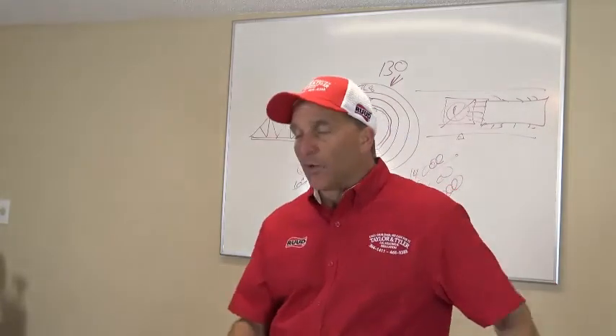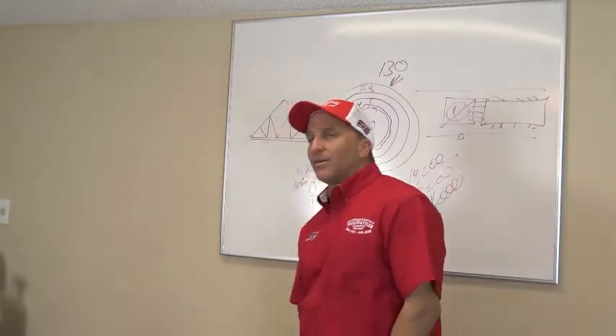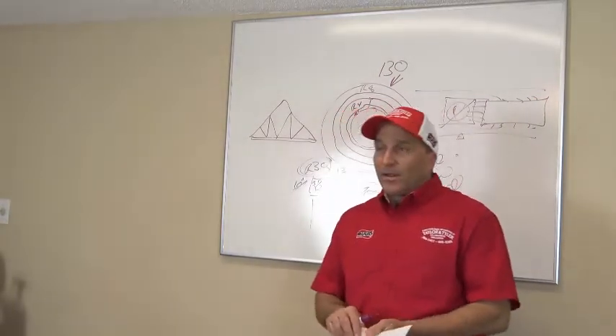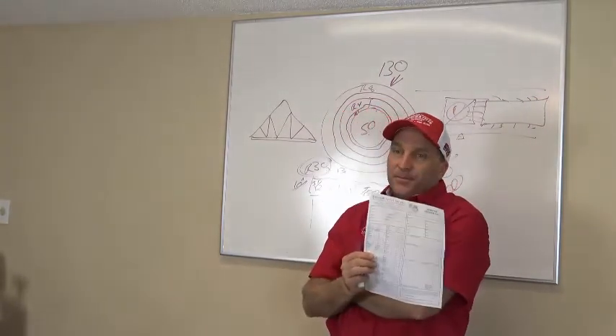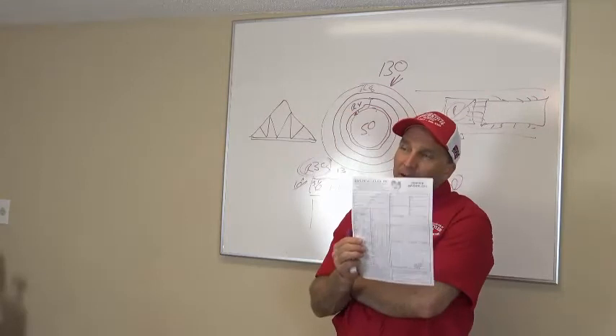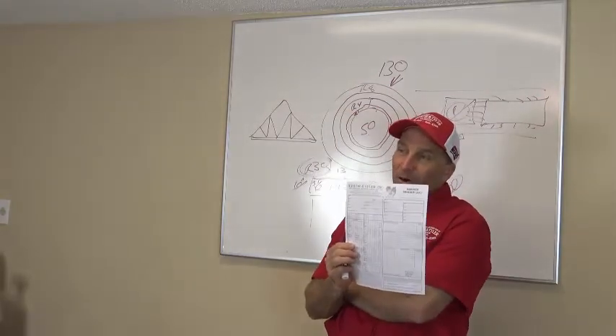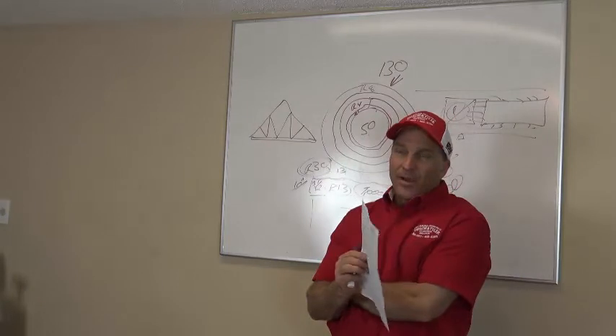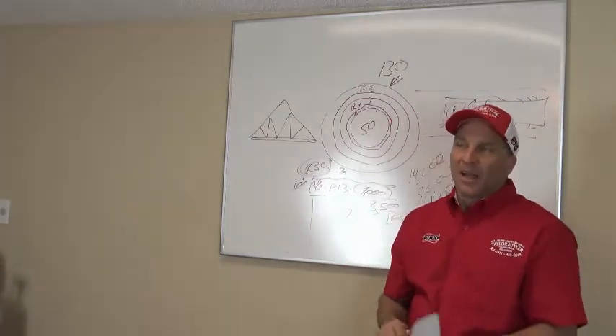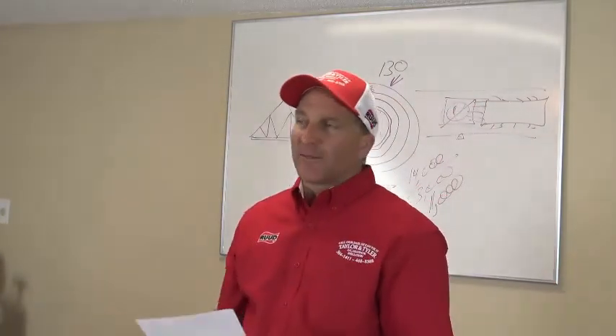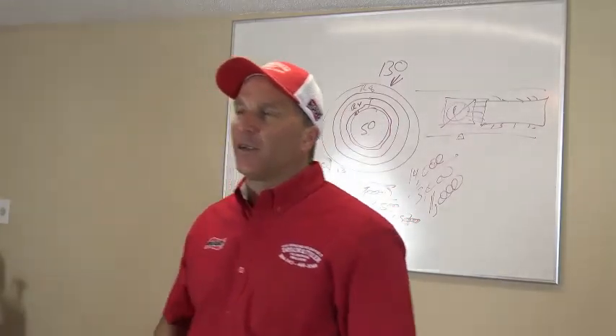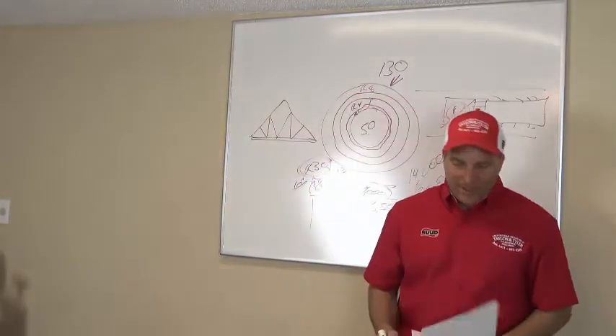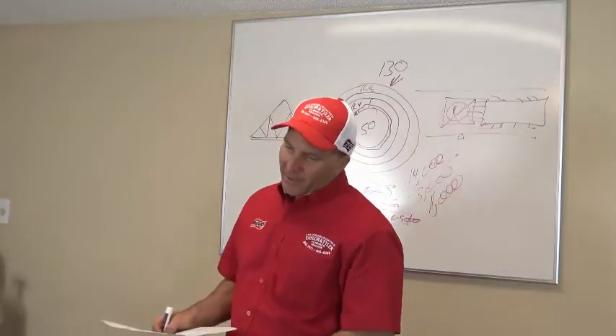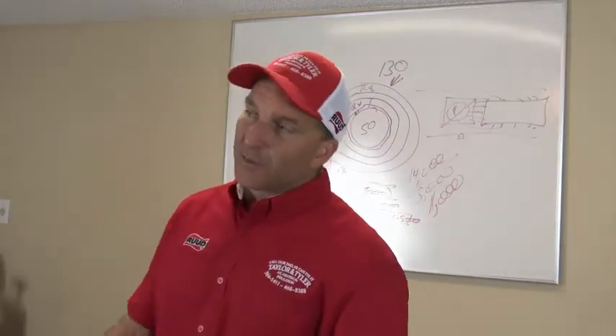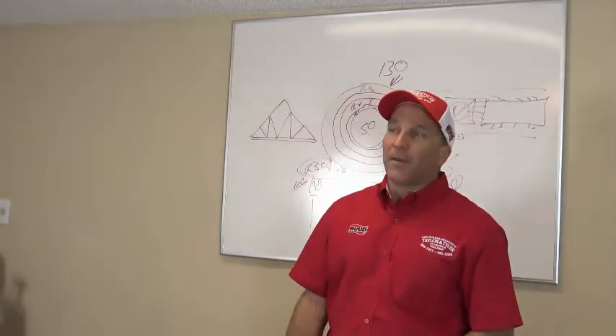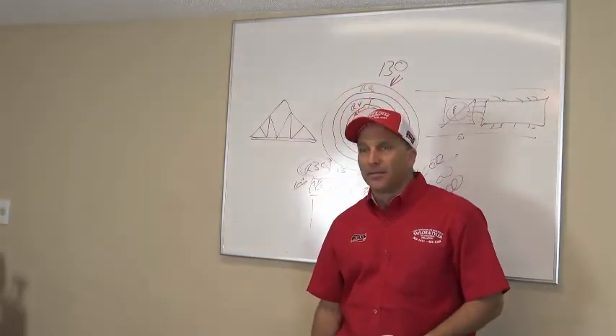Indoor air quality. What do I mean by indoor air quality in a house, guys? Well, if you just went through this whole thing right here, and you can't figure out what indoor air quality is in the house, whether it's okay, good, fair, or poor, okay? What's the humidity level in the house? 62%. Do you have a single stage air conditioning system? Yes, I do. Do you have air leaks in the return? Yes, I do. Do you have air leaks in the supply? Yep. Got dirty evaporator coil, dirty condenser systems, low on refrigerant. I got poor indoor air quality.